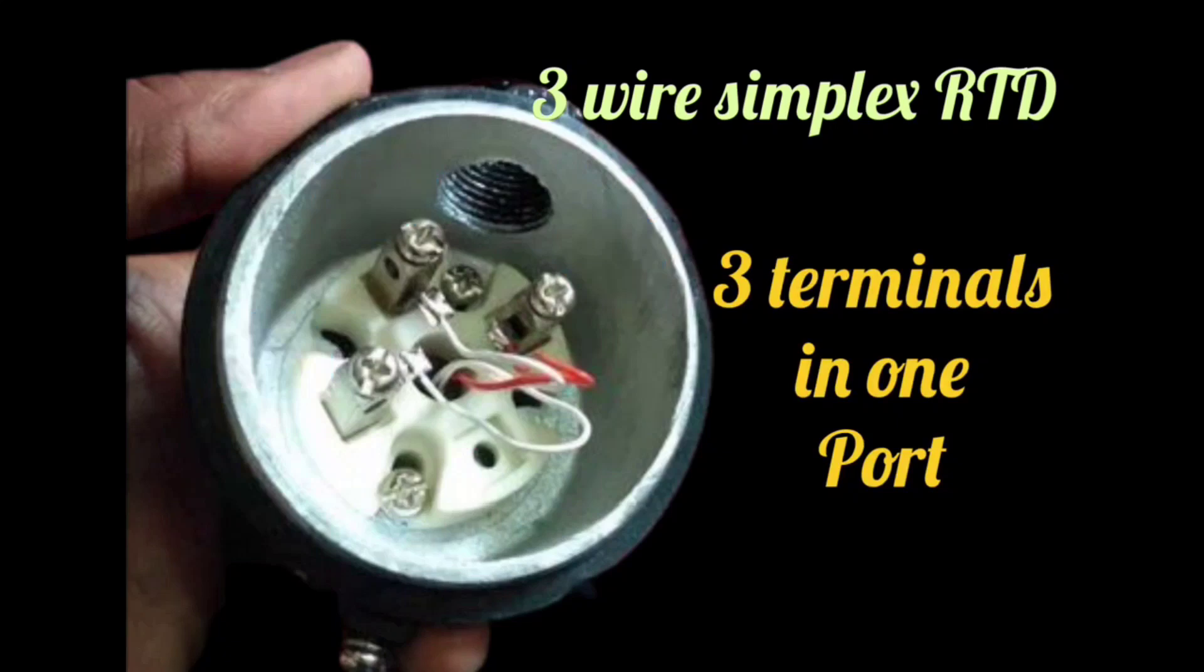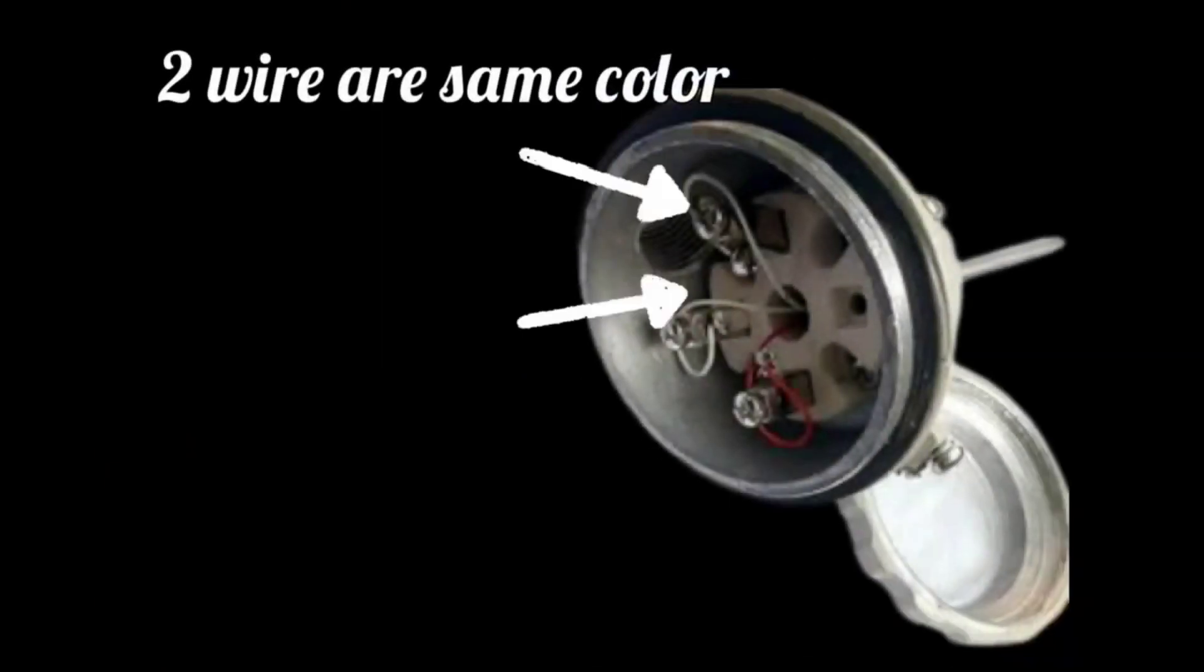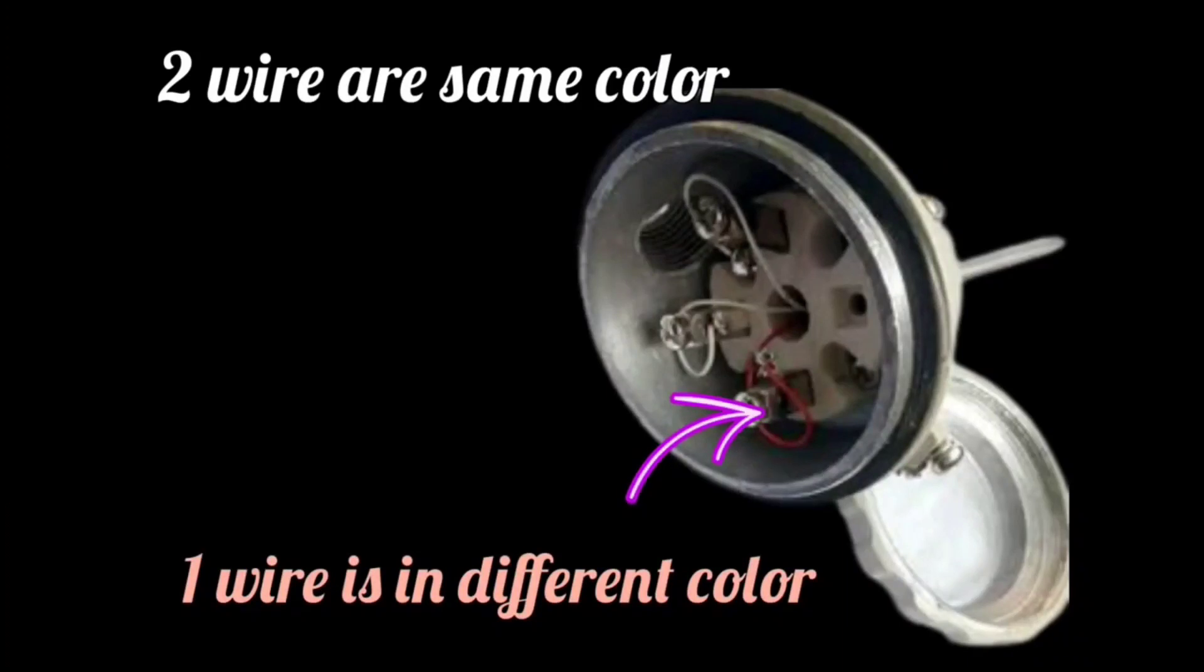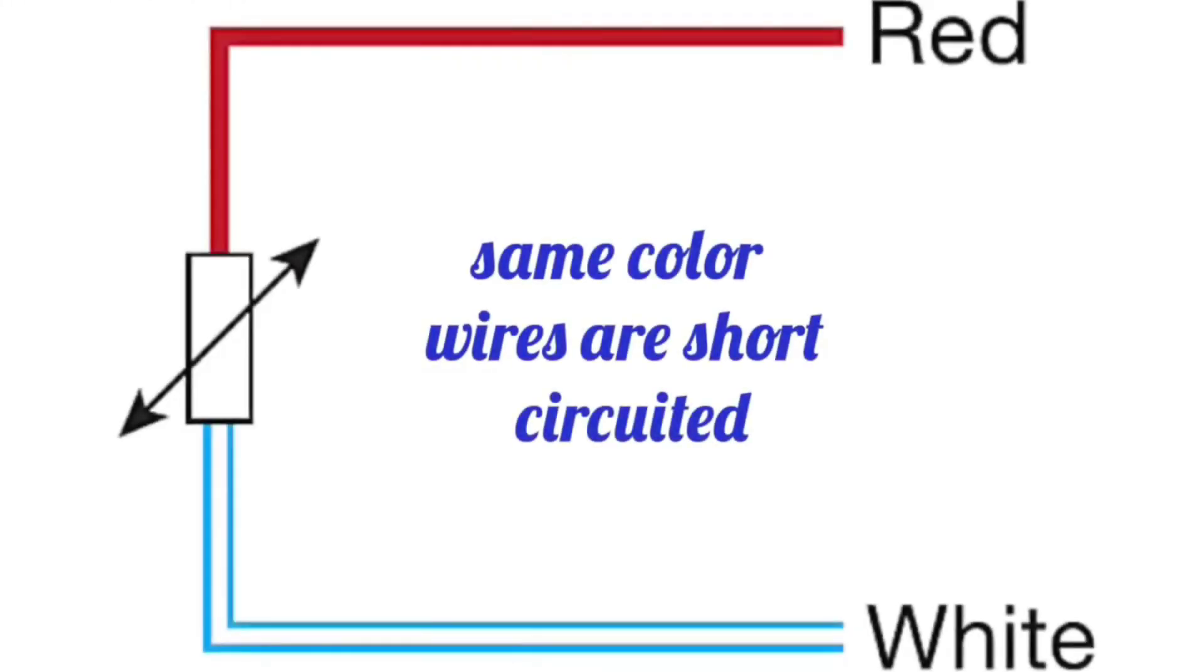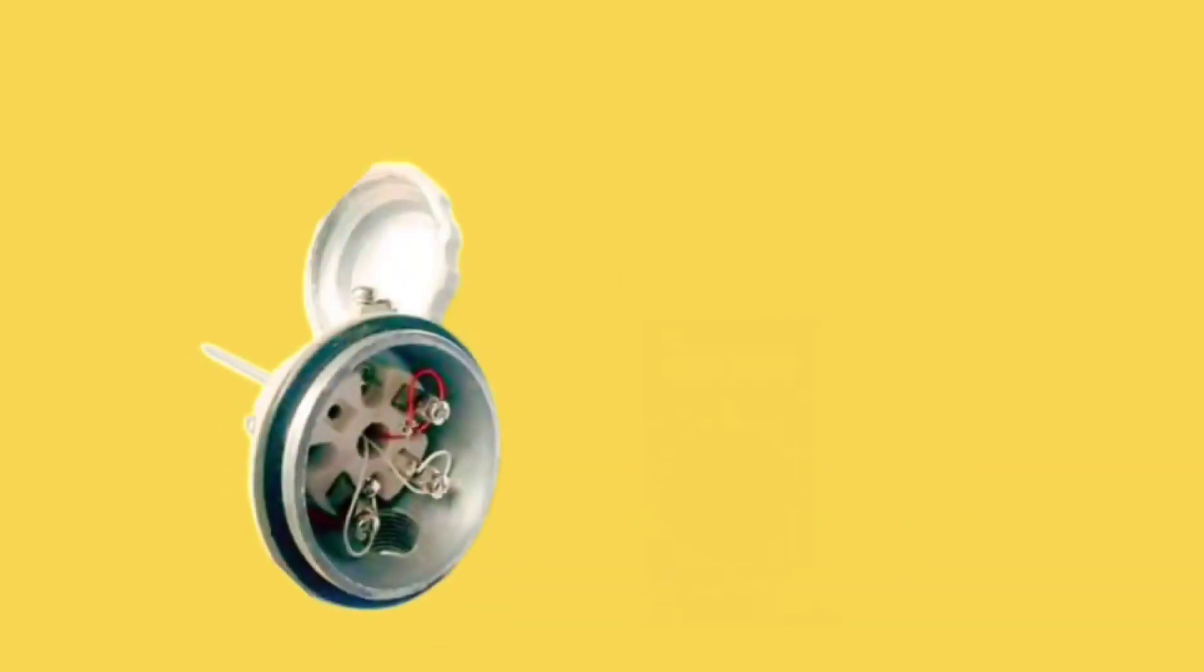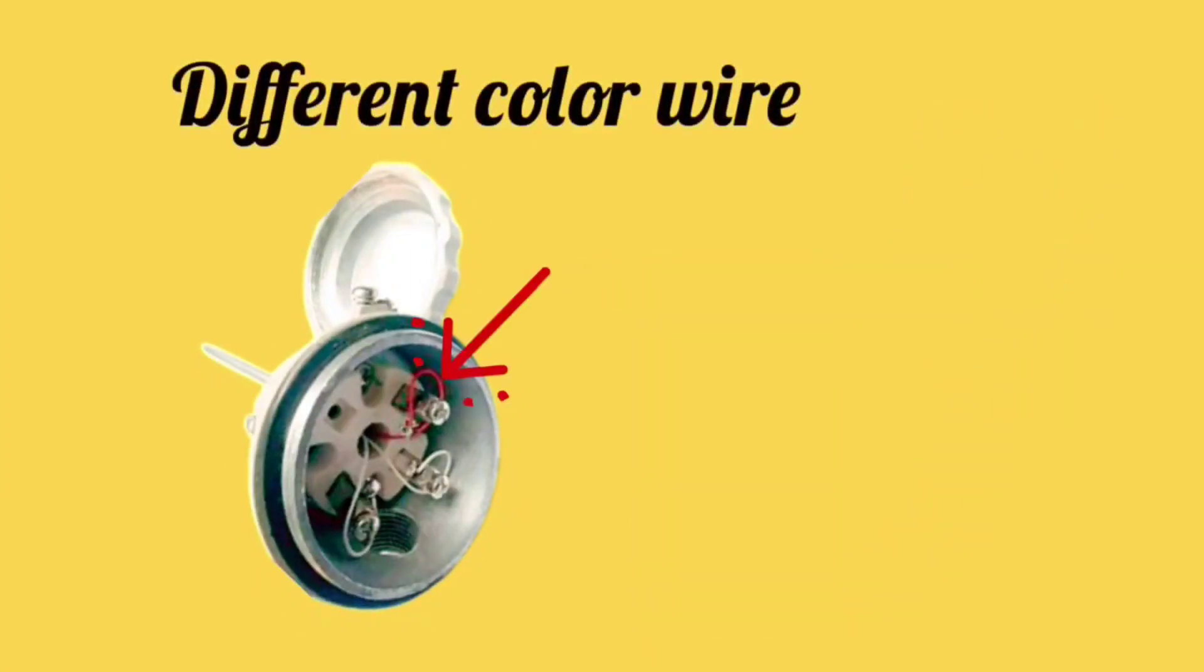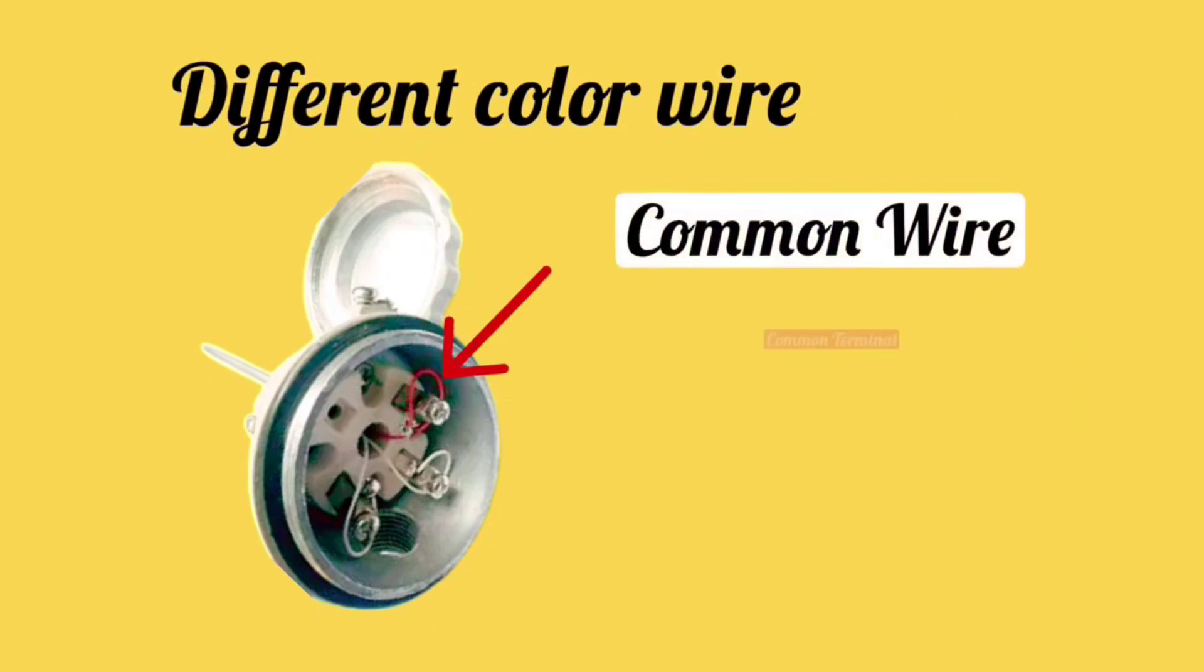And on these terminals, three wires will be connected from inside the RTD. In these wires, two wires will have same colors, and one wire will have different color. Same color wires are kept short circuit. You can check their continuity by using multimeter. And there will be a different color wire, it is also known as common wire or common terminal.